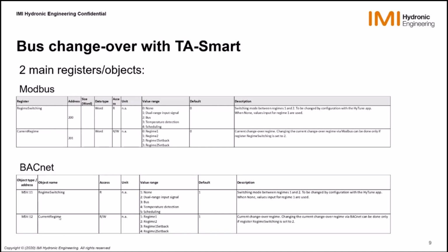In BACnet it is exactly the same, except that these are not registers but objects. You get registers 200 and 201. Here you get MSV 11 and 12, so multi-state values 11 and 12, for the BACnet objects.